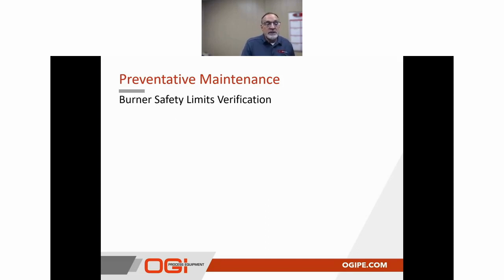The next thing that we're going to get into is evaluating the burner safeties. This process includes walking through the operation of each instrument to ensure the functionality and appropriate control response to changing conditions is correct, basically repeating the functional acceptance test conducted by OGI at our facility. Note that in this case, the safety and the temperature control logic is very similar for both pneumatic and electronic natural draft burners. Whatever general or burner specific shutdowns we may have, they are similar as far as the way they work for either of those two systems.